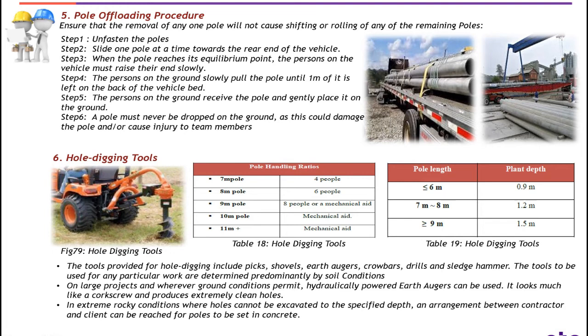Pole digging tools — a table shows different types of poles as per the length starting from 7 m up to 11 m plus, and how to handle the poles either with a number of persons or with mechanical means. Table 19 shows the hole digging depth as per the length of pole. For example: a pole less than 6 m has to be planted at a depth of 0.9 m; a pole 7–8 m has to be planted underground 1.2 m; and a pole length more than 9 m has to be planted underground 1.5 m.